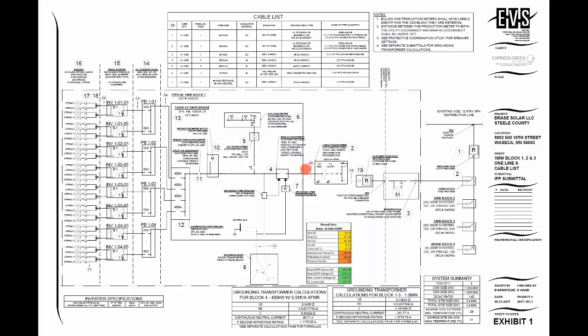At that point, it fed out to the step-up transformer, which fed to the customer's riser pole with a recloser on it, and then there was additional metering up at the medium voltage level that the utility owns. So they actually metered both up at the medium voltage level and internal to the switchboard, along with the customer having their internal metering as well.